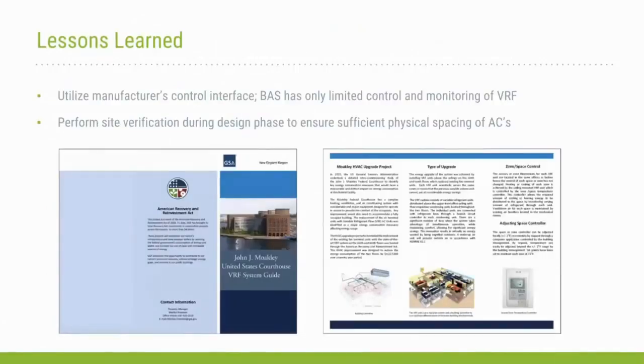So as far as lessons learned, using that manufacturer's control interface was a lesson learned. The BAS does only have control and monitoring of that subsystem. And performing that site verification during design to make sure there's sufficient physical space for those units was also an important lesson learned. A few other things that we did to make that really work out is that we did send the O&M to a multiple day offsite. We found it was important because our O&M contractor was not familiar with how a VRF system would work and how to maintain it. So it made good sense to go ahead and spend that money, and we actually got 6 of the contractor's O&M staff through training. And I think that was a good lesson learned and something that we would like to replicate in other and further projects. Next slide, please.